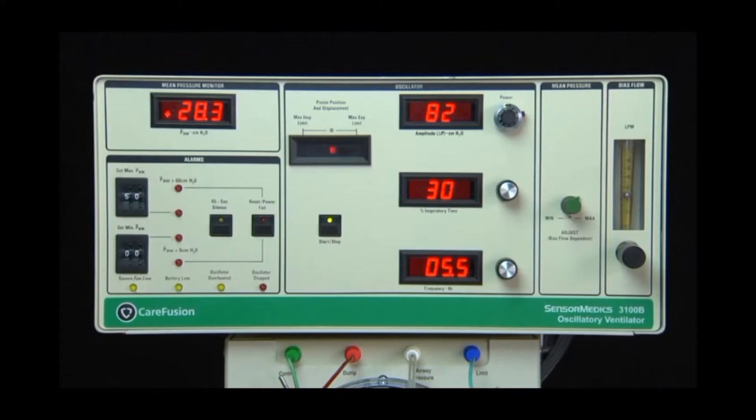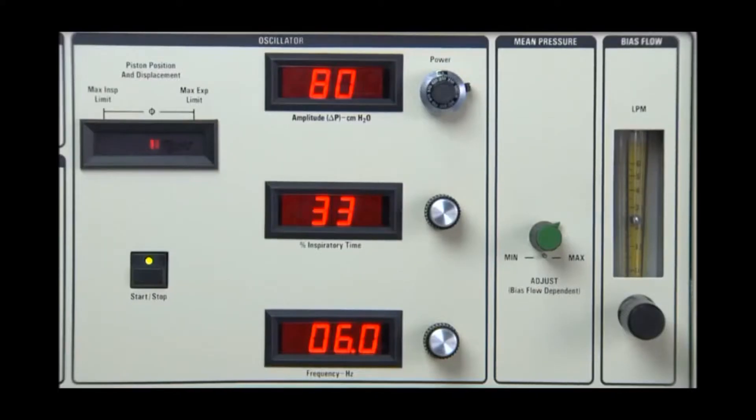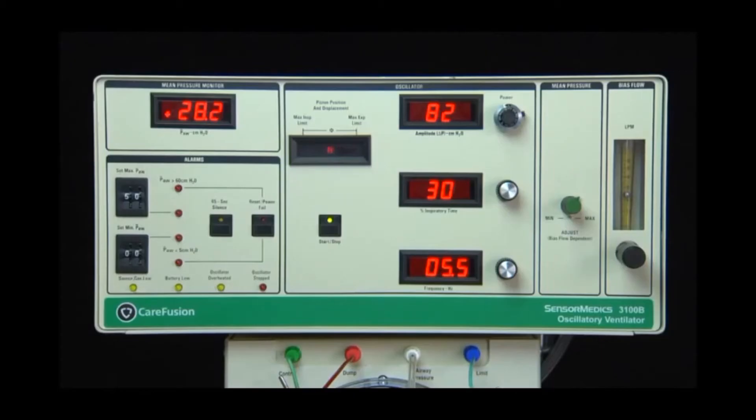In this case, chest wall movement will either be diminished or completely absent. The Piston Position and Displacement Indicator provides the operator with information on the position of the piston relative to its mechanical limits and the control settings. The 3100B features auto-centering and thus requires no intervention by the operator to maintain piston centering.